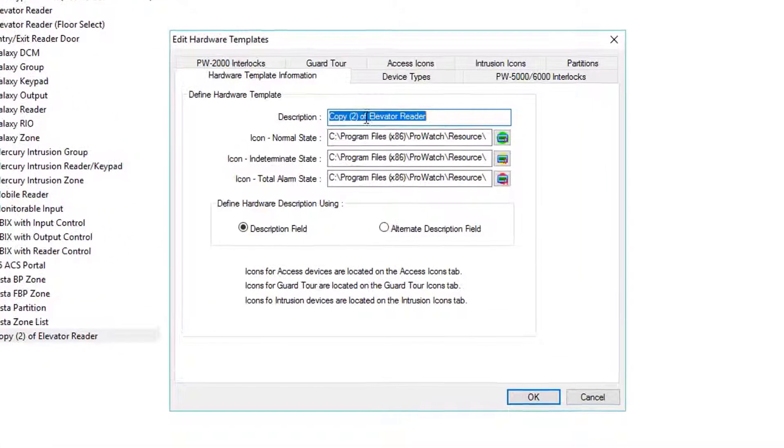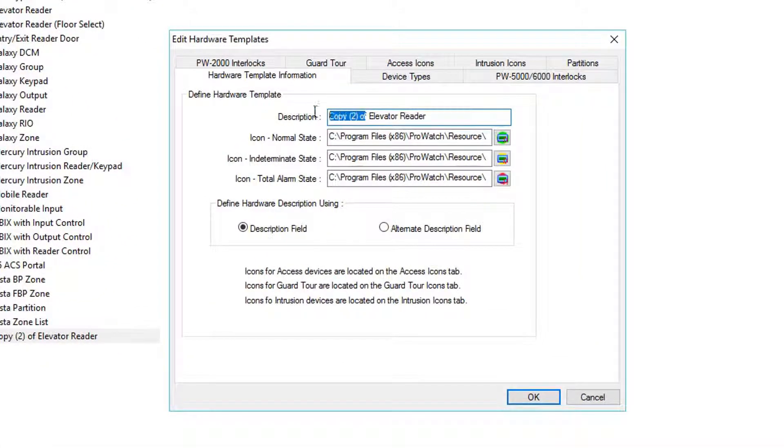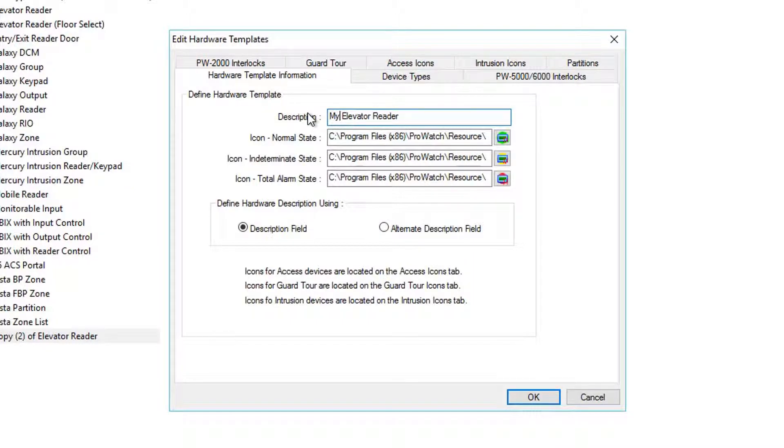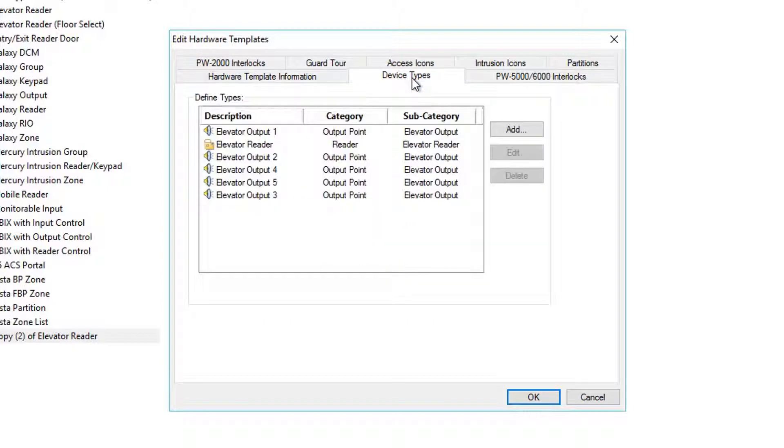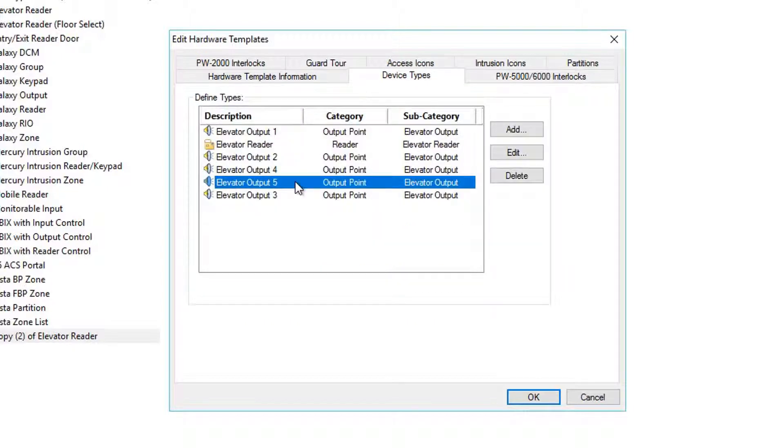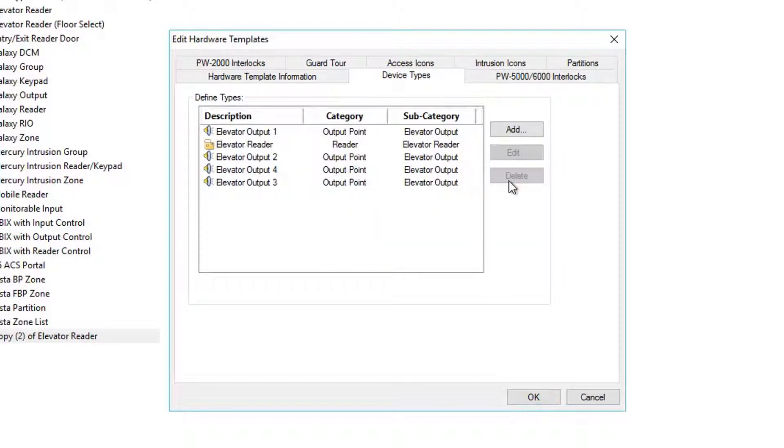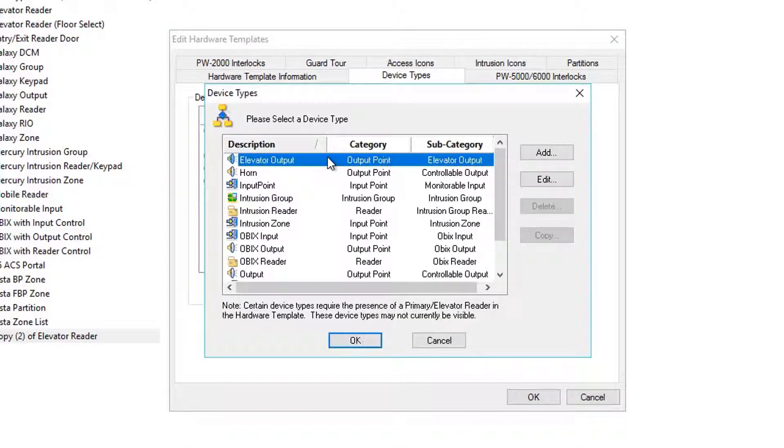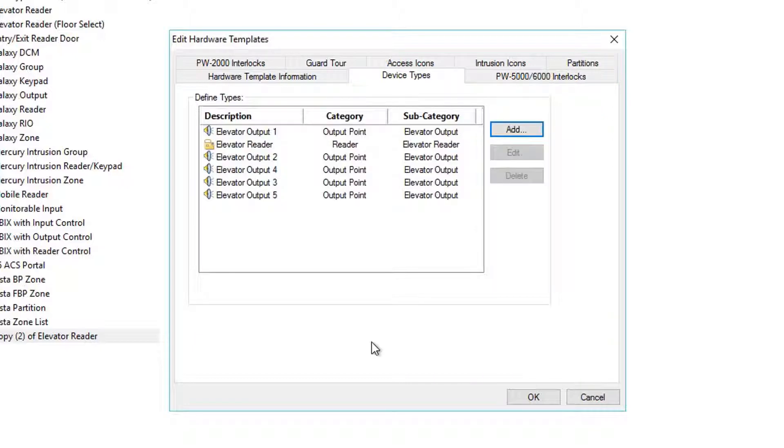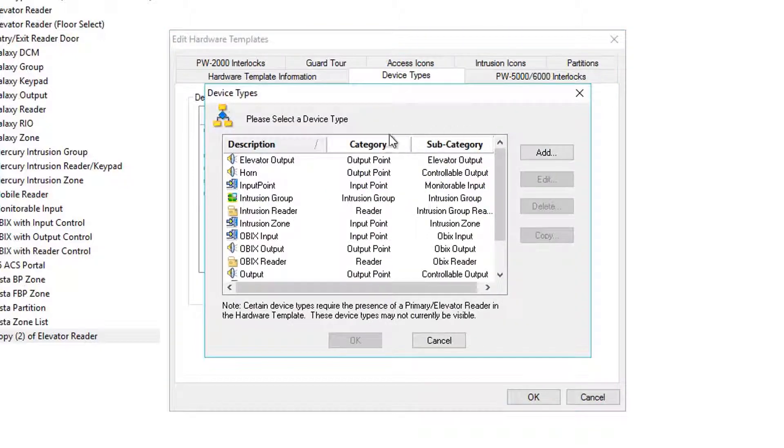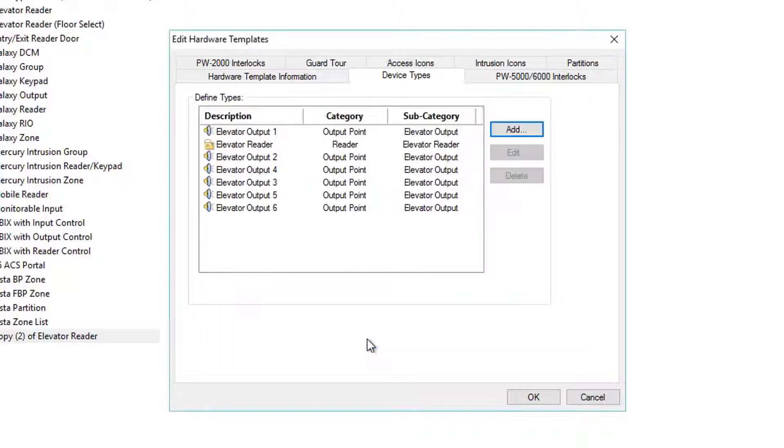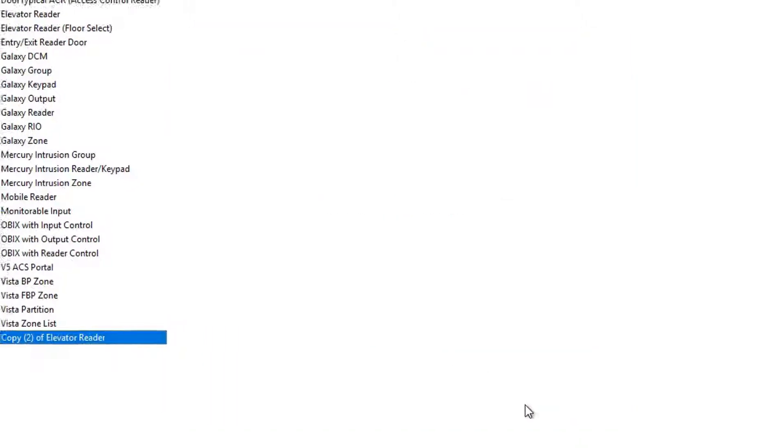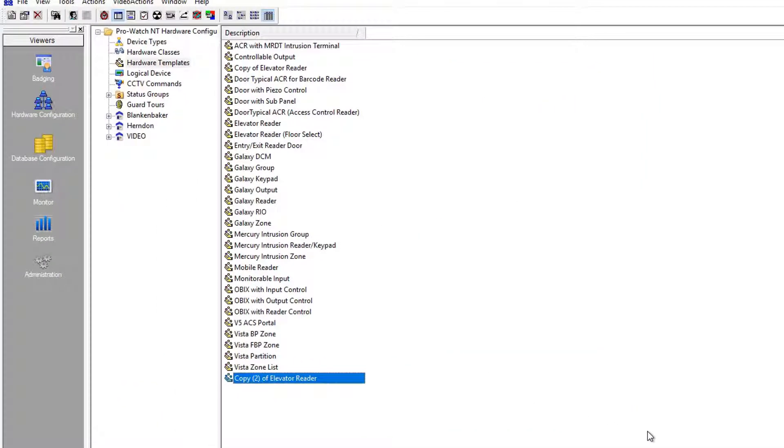Next, double-click on our new copy and update the name to My Elevator Reader. On the Device Types tab, you want to make sure you have the correct number of outputs per floors for your elevator. Highlight existing outputs that are too many and click the Delete button, or click Add and add additional elevator outputs. In this example, our elevator has six floors. Click OK to save.